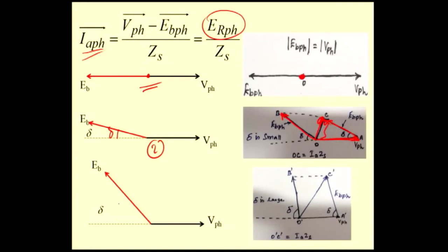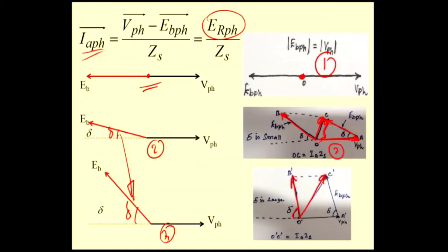In the third case, you are increasing the load further, so delta increases more. Comparing second and third diagrams: delta is less in second case, delta is more in third case, because load is increased. Er phase magnitude also increases. First case: Er phase is zero because delta is zero. Second case: delta is somewhat more, so Er phase is more. Third case: delta is even more, so Er phase is further increased. Er phase increasing means Ia increases. In any motor, if you increase the load, the current will increase.